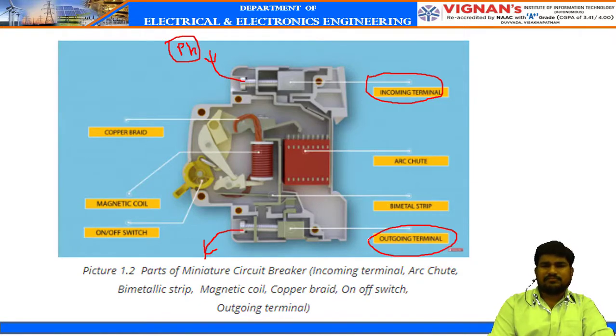The next one: whenever the current exceeds the limit because of overloading, what happens? There is a special mechanism, the bimetallic strip. The strip will expand or contract based on the current flowing through it. If the current exceeds the limit, the bimetallic strip expands because of the heating effect, and it opens the circuit by providing a trip signal. That means the on-off switch will be tripped down whenever the bimetallic strip expands. So this is for overloading.